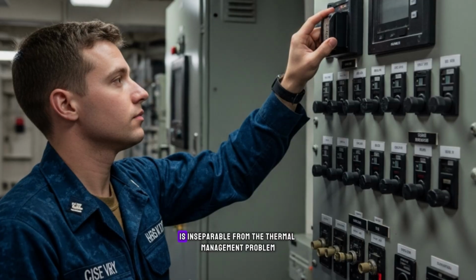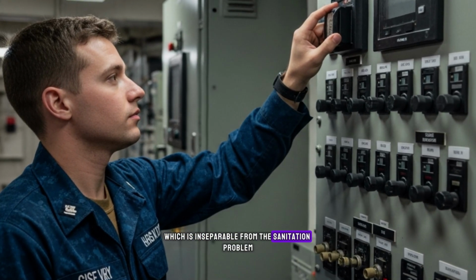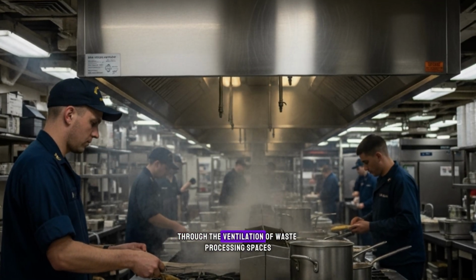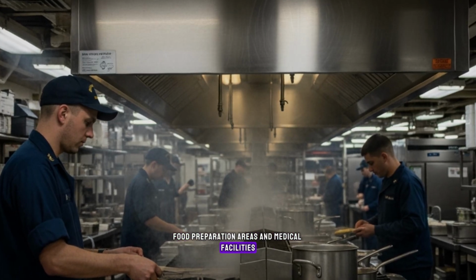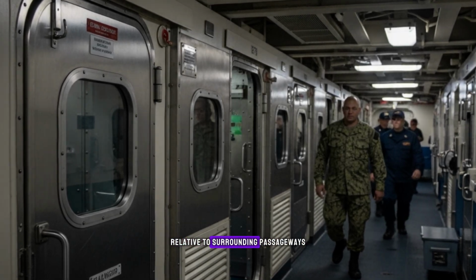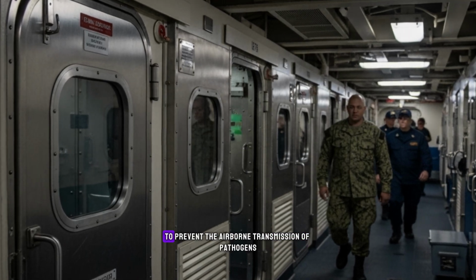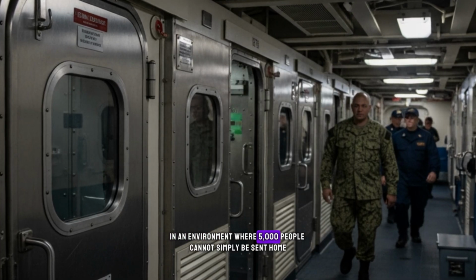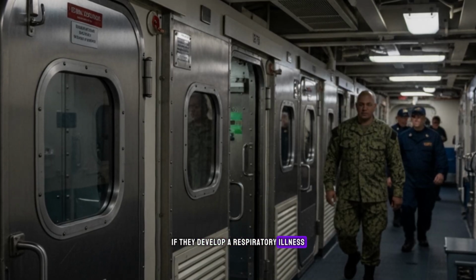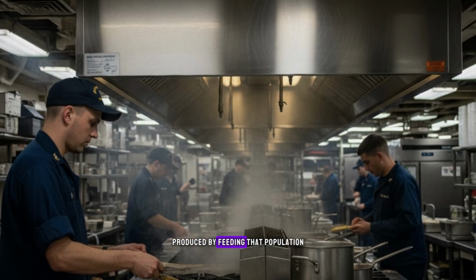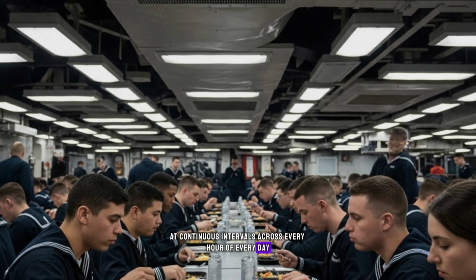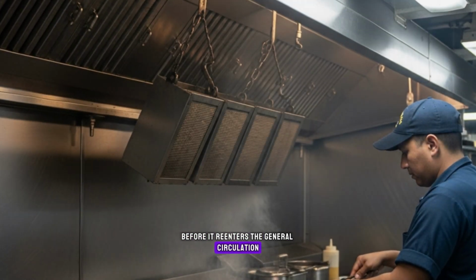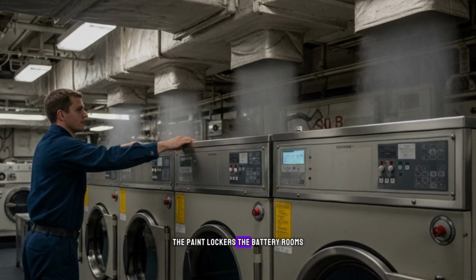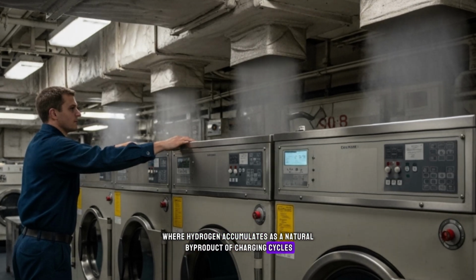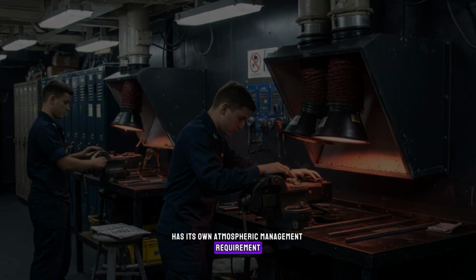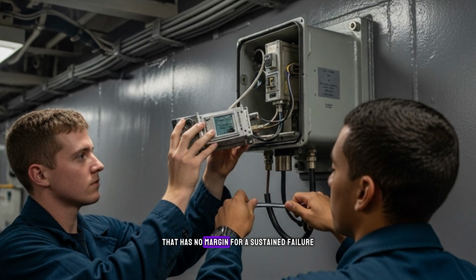The atmospheric management problem is inseparable from the thermal management problem, which is inseparable from the sanitation problem, which connects directly back to air quality through the ventilation of waste processing spaces, food preparation areas, and medical facilities. The ship's sickbay ventilates under negative pressure relative to surrounding passageways, exactly like a hospital isolation room, to prevent airborne transmission of pathogens in an environment where 5,000 people cannot simply be sent home if they develop a respiratory illness. The kitchen exhaust systems handle the grease-laden air produced by feeding that population continuously, routing it through filtration before it re-enters general circulation. The laundry facilities, the workshops, the paint lockers, the battery rooms where hydrogen accumulates as a byproduct of charging cycles — every one of these spaces has its own atmospheric management requirement, and every one connects back to the same integrated system that has no margin for a sustained failure.